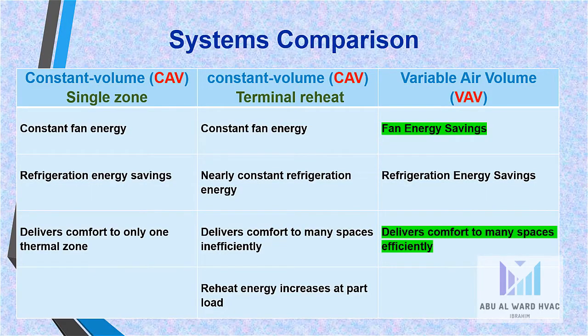In the system comparison: the normal CAV single zone has constant fan energy and refrigeration energy savings but delivers comfort to only one thermal zone. The terminal reheat CAV has constant fan energy and nearly constant refrigeration energy, delivers comfort to many spaces, but reheat energy increases at part load, which is a loss. The VAV system offers the best fan energy savings, the best refrigeration energy savings, and delivers comfort to many spaces efficiently — making VAV the best system among the three.